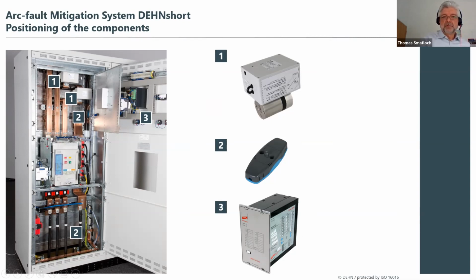Yeah, the light sensors in this case are located in different positions, because such an arc fault can happen in different positions. And to verify the signal, here we have two of those sensors. One is mounted here, the other one is mounted over there, and the control unit is here within the door of this cabinet. Yeah, so when this is a larger installation for, let's say, big hospitals or something like this, then they usually put it in an extra part of a cabinet.